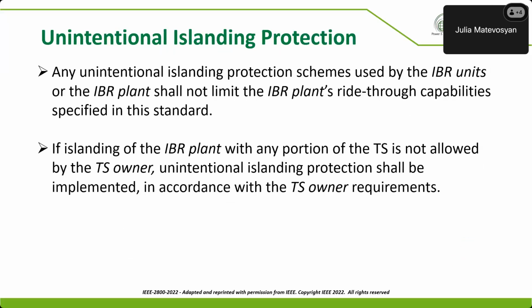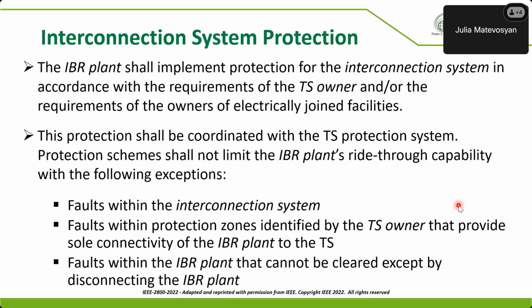Unintentional islanding, as I mentioned earlier: most transmission entities out there today would like some sort of anti-islanding protection in place. Some may allow or rely on the anti-islanding protection that is built into the inverters or the wind turbine generators. And some may require transfer trip based protection. So the standard says any islanding protection used by units or the plant shall not limit the plant's ability to ride through. And if islanding protection is required by the transmission owner, then that protection shall be implemented as specified by the transmission owner.